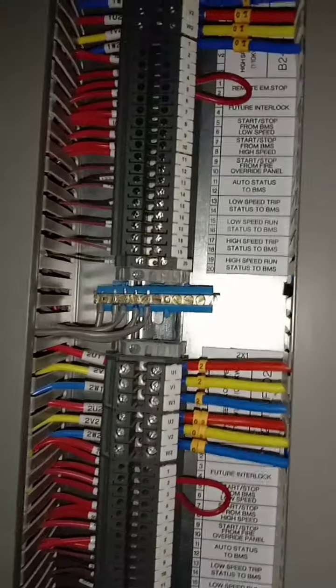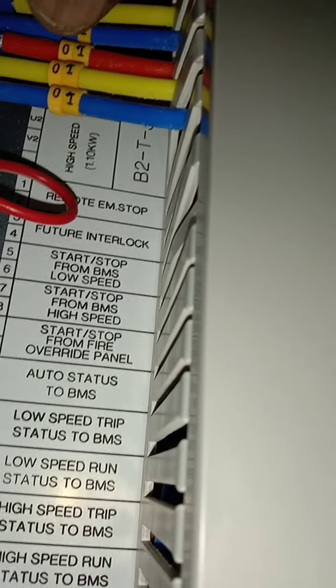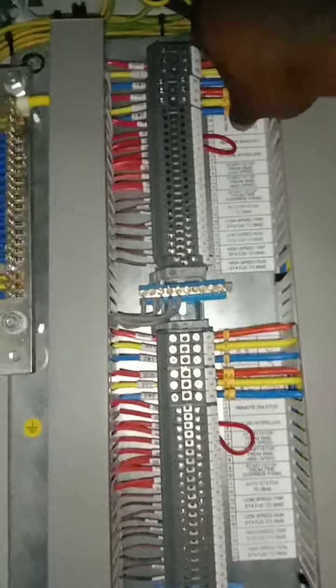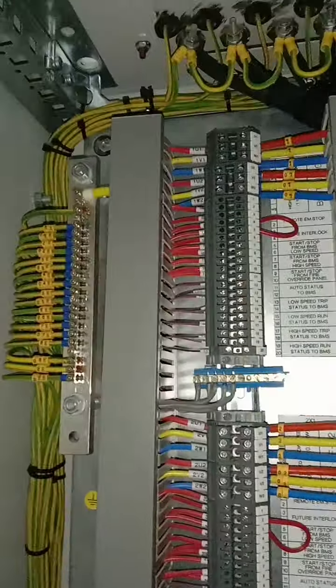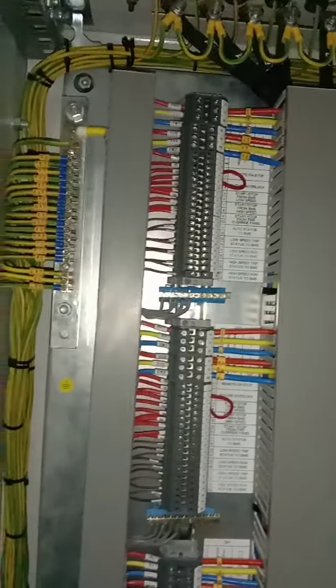So these are the two runs now. For motor 1 we have the first run, and then the second run, which is connected to the motor with the jet fan. The first will come to the low speed side, and the second comes to the high speed side. As you can see, below we have the high speed, which is 1.10 kilowatts, and the low speed, which is 0.23 kilowatts. So the high speed cable will connect to the high speed, and the other cable to the low speed. Based on what you see on the load schedule, calculations have been done for the high speed to determine the size of cable to be used.